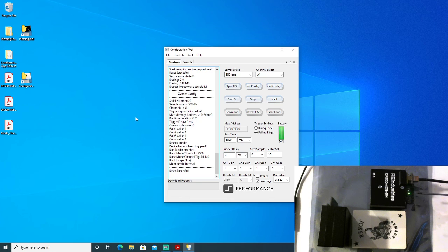It finished, automatically goes back to idle mode, and then has the previously triggered LED to indicate to the customer that the device has been triggered and needs to be reset, and it needs to receive a memory erase command before any more data is captured.